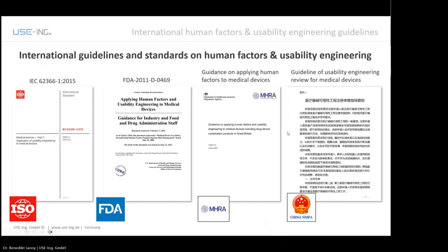So besides the previously mentioned IEC 62366 standards, there are more international standards and guidelines that help us to fulfill the human factors and usability engineering requirements. The most relevant ones from my perspective are the IEC 62366-1, the FDA guidance, of course, since the US market is still the biggest market for medical devices.